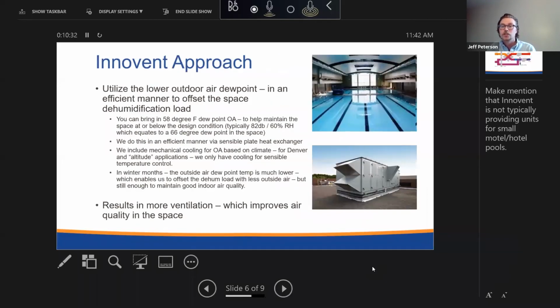So how is Innovent's approach different? We actually use outside air as our primary means of dehumidification. So from a mechanical efficiency standpoint, especially in a place like Salt Lake, right, where your design dew point day is a relatively low dew point temperature, we can use that low outdoor dew point to offset the space dew point and offset the dehumidification load primarily, right? We do some mechanical cooling because when it's not a design dew point day, but it's a design dry bulb day or the hottest day of the year in Salt Lake, you don't want to bring in so much outside air that you overheat the space, right?